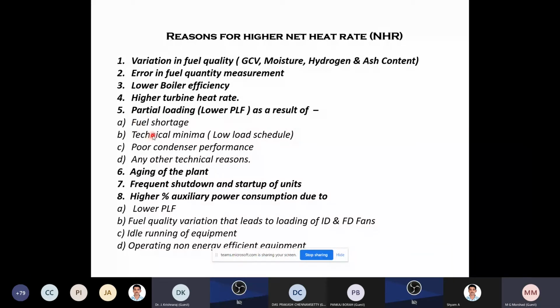Technical minima. Nowadays, in the ABT regime, the Central Electricity Authority or the RLDC will tell you to restrict your load to 150 for 2 hours or 30 hours, like that. That is called the technical minima, the low load schedule. Then poor condenser performance. Any other technical reason, the partial loading will be there. So this partial loading is also reflected in the net heat rate.